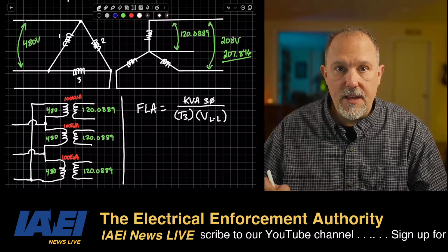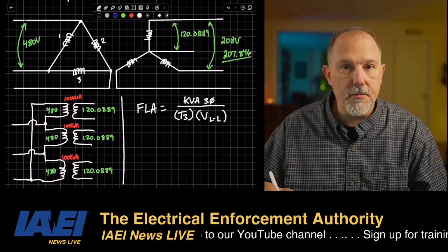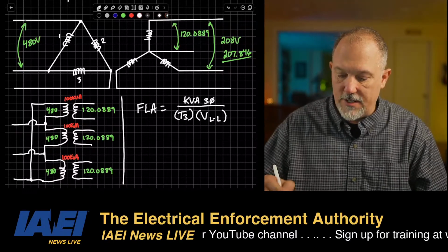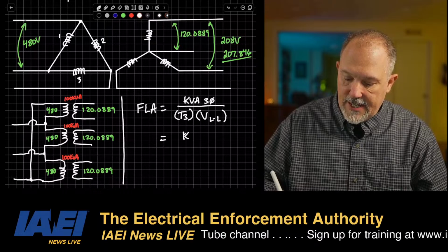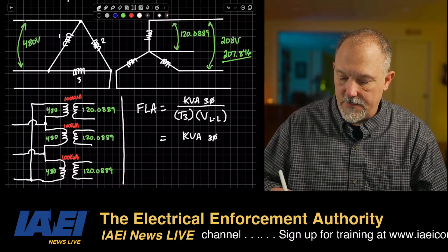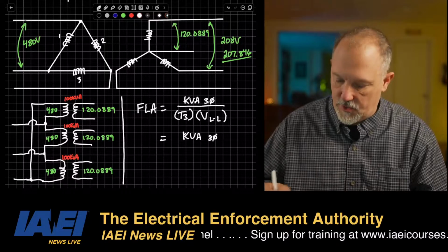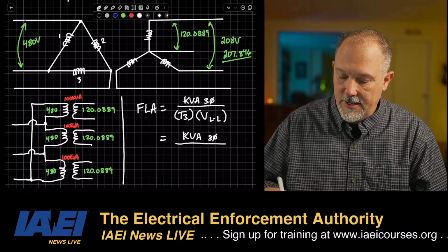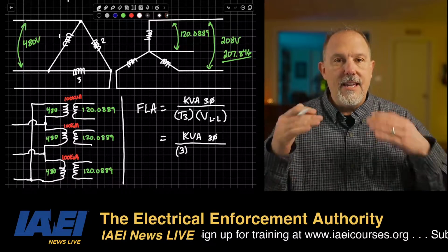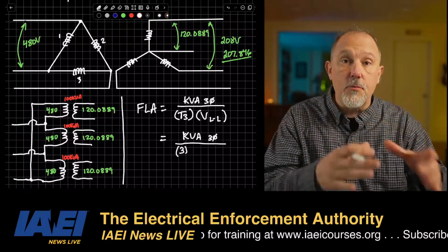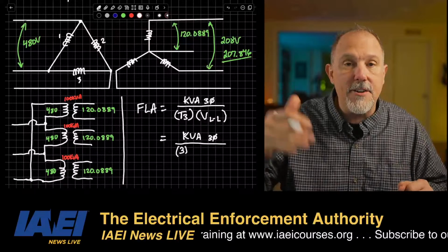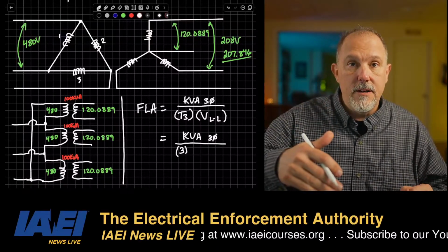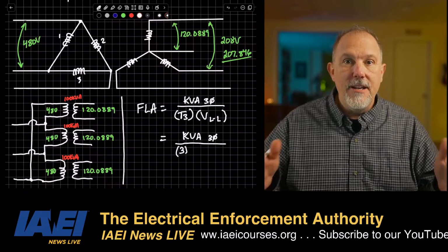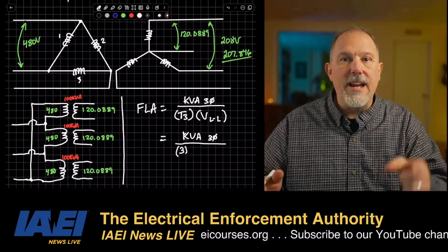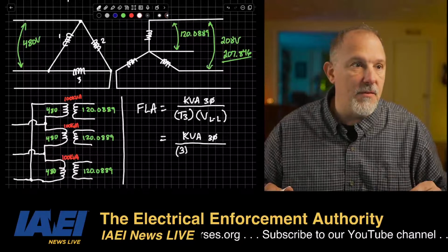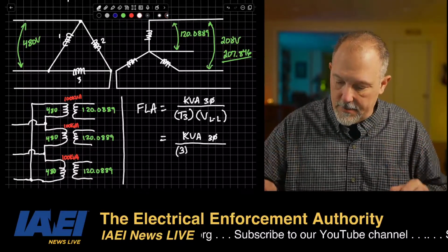So kVA three-phase divided by the square root of 3 divided by the line-to-line voltage. And where does that come from? If I take kVA three-phase, and I've done this before and people don't like when I do this, but it helps us understand. Divided by 3. kVA three-phase divided by 3 gets me to 3 single-phase transformers. So a 300 kVA bank of 3 single-phase transformers. 300 divided by 3 is 100. I have 3 100 kVA transformers. All right? Follow me here.